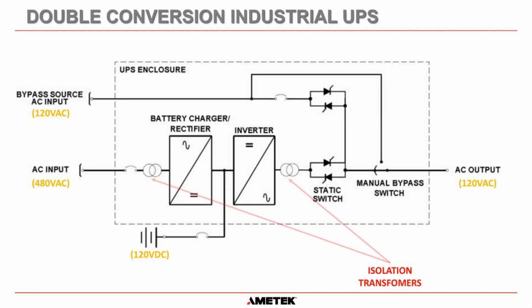But with this transformer here, there is no electrical connection between the primary and the secondary. So that prevents any DC getting back onto the MCC that feeds the AC input. And this transformer here prevents any DC, if there was a failure in the inverter, getting onto your AC load circuits, because an isolation transformer will not pass DC. It's impossible. So that's one of the main differences between a commercial and an industrial UPS.